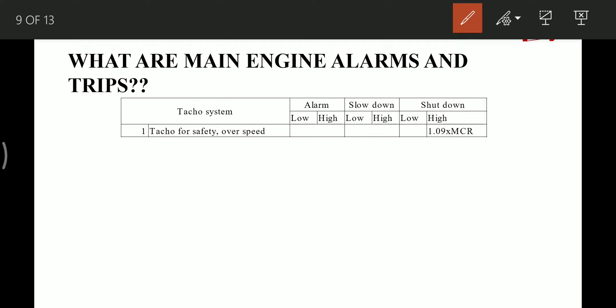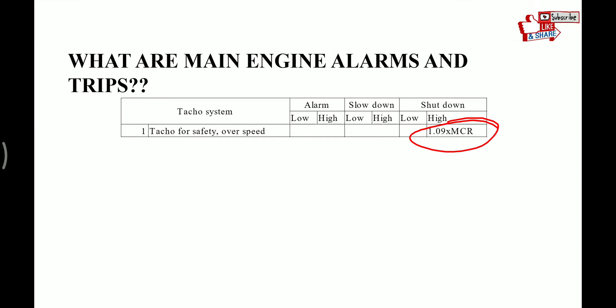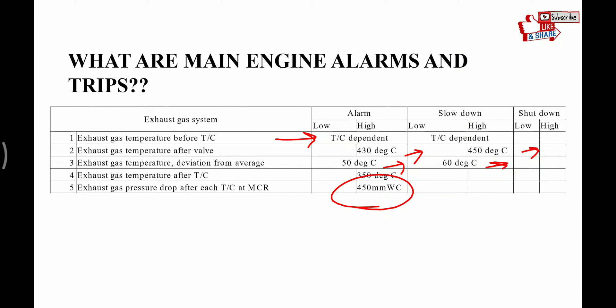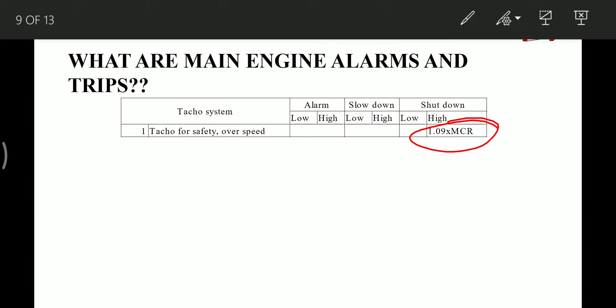The Tacho system: the Tacho sensor is provided for overspeed protection. It shuts down the engine when its value reaches 1.09 times the MCR value — that is 109% of MCR speed. This is basically the overspeed alarm.